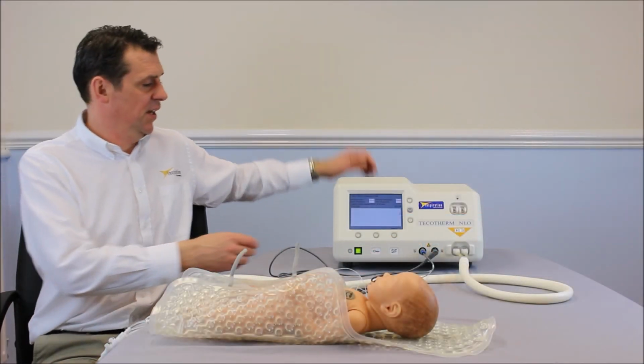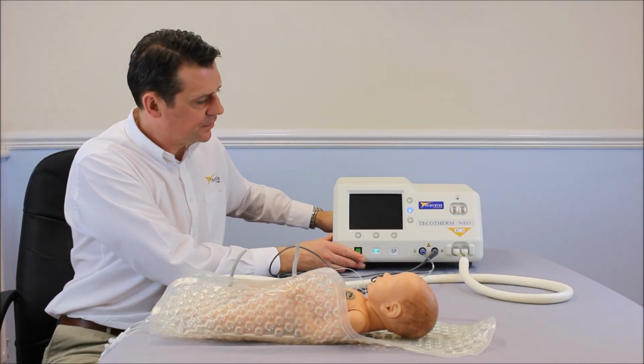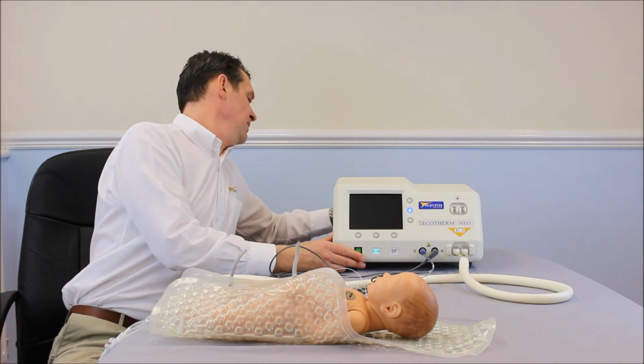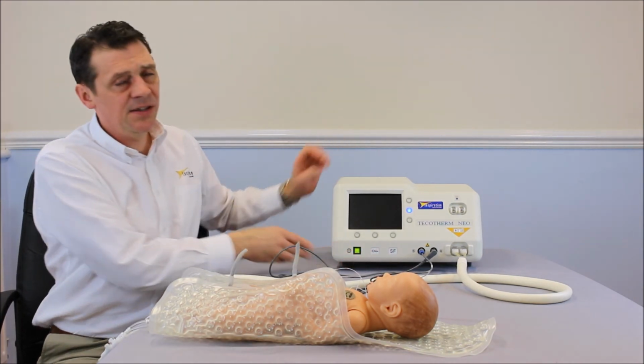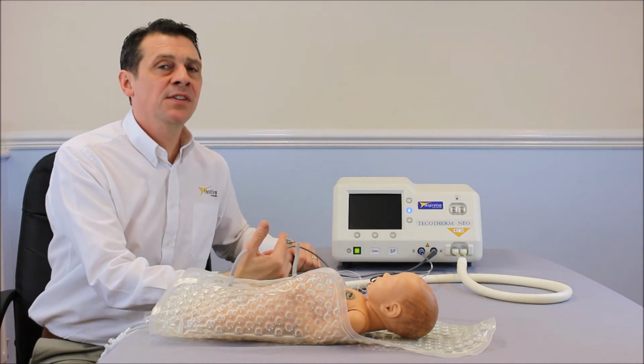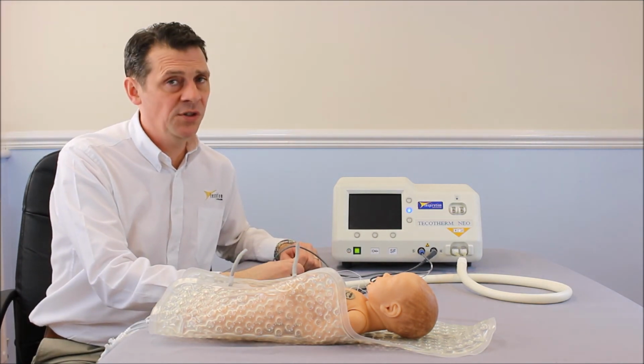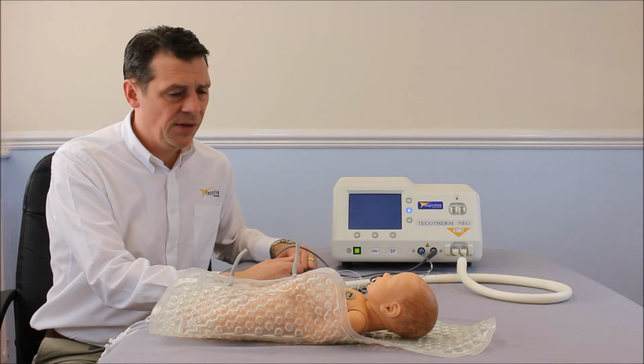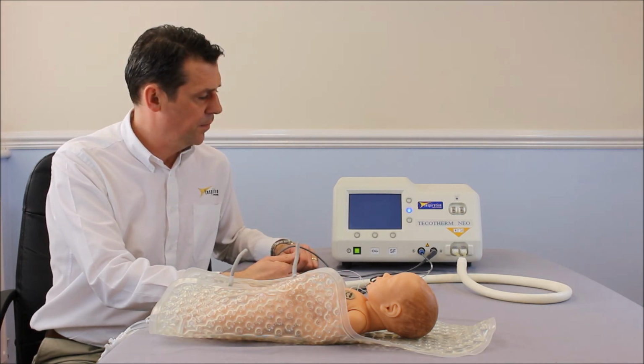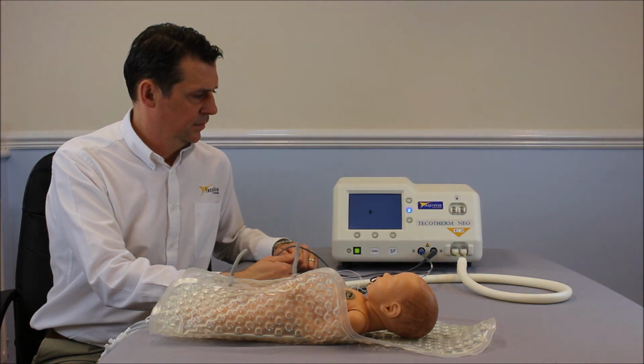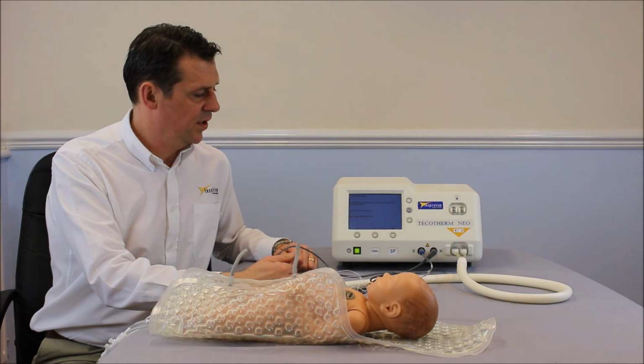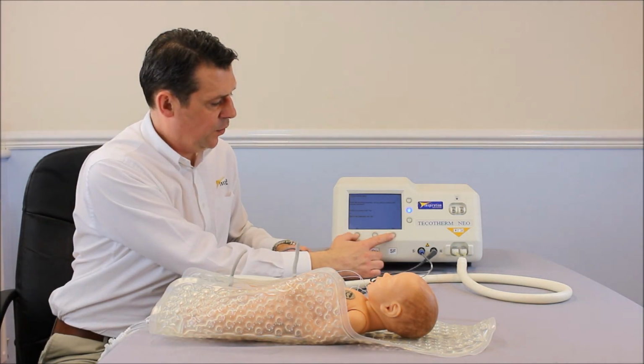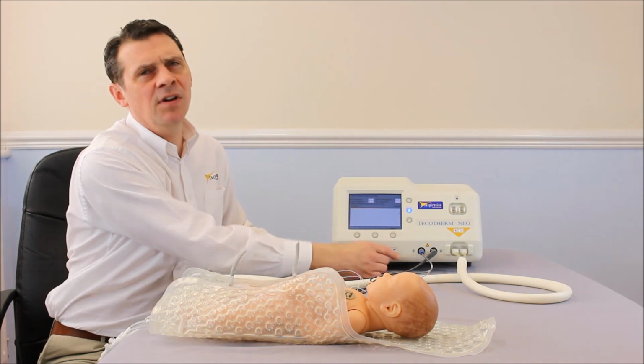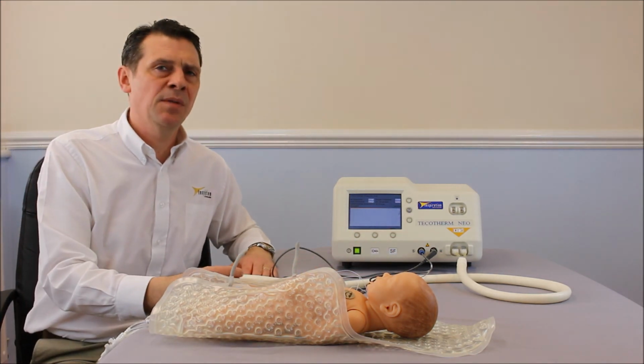If you lose power with your machine, you will get a further alarm. What you need to do is reconnect your power, allow the system to reboot up, and that will then give us an option of continuing on the therapy that we had or changing the therapy if you wish to do that instead. We'll allow this to boot up. And you have two options. Do you want to continue with yes, or change the treatment with no? We'll press yes to continue. This is very useful for transport if you're taking from a hospital to an ambulance.